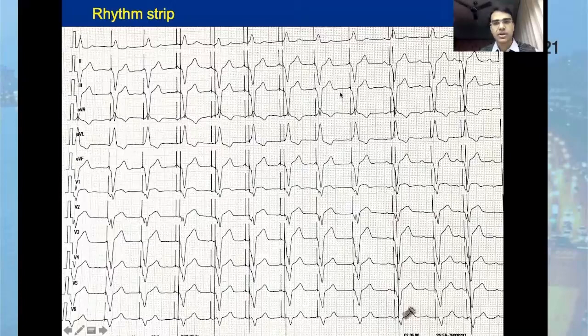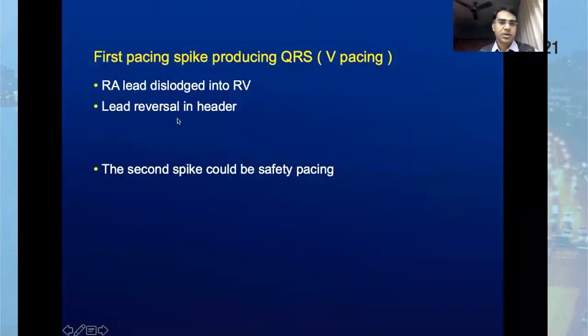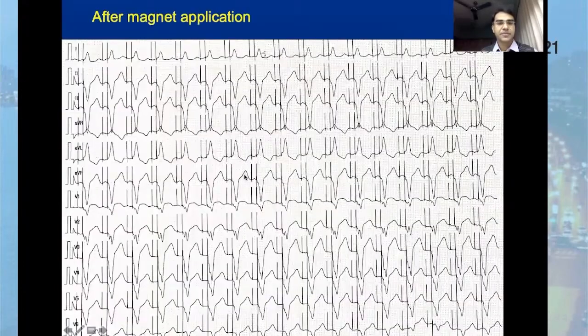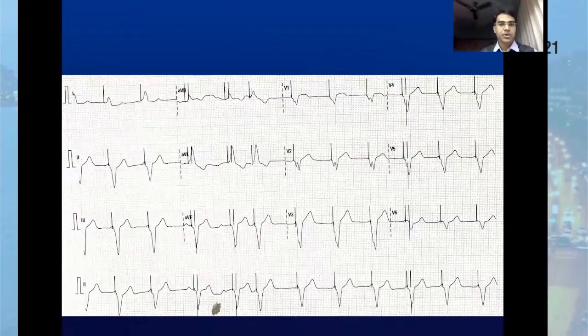So at this time, the two possibilities were these. When we have two very closely placed pacing spikes and the first pacing spike produces a QRS complex, we always have to think about an RA lead dislodging into the RV, or a lead reversal in the header. The second pacing spike could be because of safety pacing. But as there was a magnet ECG available, we found that with magnet, there was consistent A and V pacing with good capture of the atrium and ventricle. So both these possibilities seemed unusual or less likely.